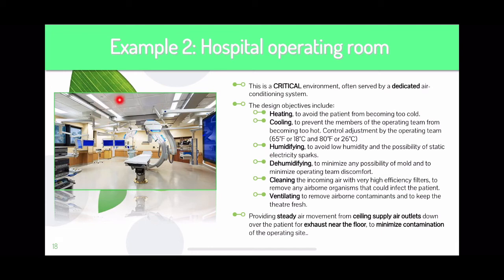Sometimes you need to dehumidify the room after humidifying to minimize any possibilities of mold on ceilings, walls, cabinets, and fabrics inside the operating theater. For cleaning, we must maintain incoming air through high-efficiency filters that remove any airborne organisms and dust that might infect patients or induce allergies. For ventilation, we must remove airborne contaminants and keep the operating theater fresh by providing steady airflow movement from ceiling towards the floor around the room.